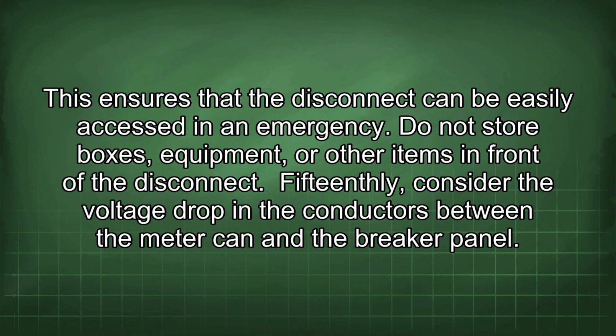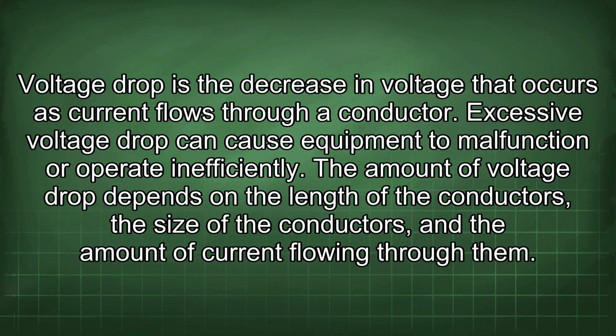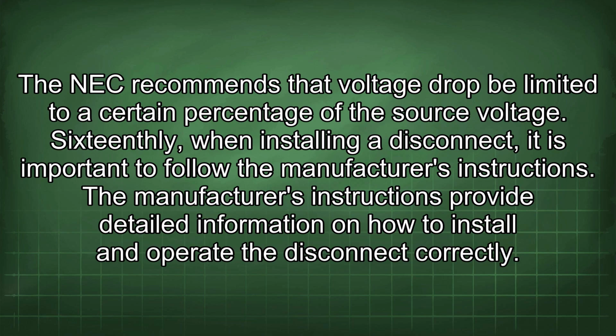15th, consider the voltage drop in the conductors between the meter can and the breaker panel. Voltage drop is the decrease in voltage that occurs as current flows through a conductor. Excessive voltage drop can cause equipment to malfunction or operate inefficiently. The amount of voltage drop depends on the length of the conductors, the size of the conductors, and the amount of current flowing through them. The NEC recommends the voltage drop be limited to a certain percentage of the source voltage.